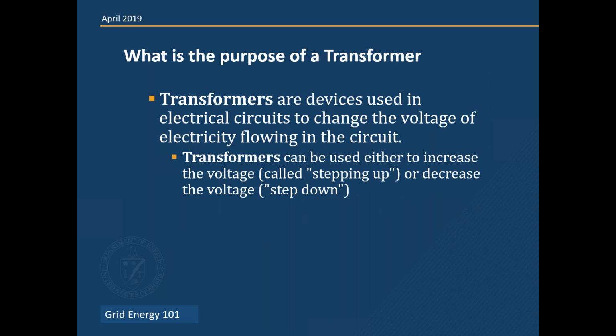One of the big pieces of equipment out there on the system is the transformer. They come in various sizes, and again, they can either step it up to a different voltage level or step it down. Transformers are really expensive and hard to come by the bigger they get. Your average pole top transformer, which we'll take a look at in a couple of minutes, is fairly inexpensive to maintain and replace. But power transformers at EHV substations take years to build, and so they're kind of costly. Next slide, please.